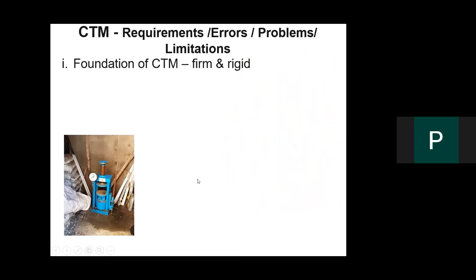You can see different types of variations available. Normally the variation you will see in hand machines. Sometimes people are not aware. Sometimes the client or consultant or somebody else insists you have to have a CTM machine at your site. So what do they do? They go to any bazaar or market and get a nice second hand, third hand, fourth hand machine. They just install the machine. They never go for calibration. They never use it properly, and just say, yes okay fine, this is my machine, I put it there.